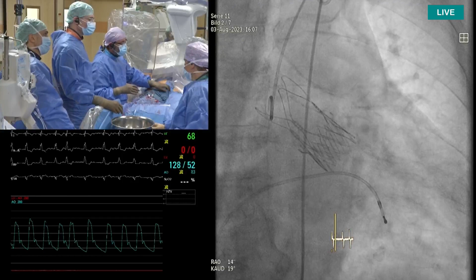If I can make just one comment, I think for the audience it's important to highlight that, contrary to other self-expanding devices where a shallow implant has been recommended to reduce pacemaker rates, with this device, if you want to take full advantage of the radial forces, you have to deploy it at the exact position as Mohamed did just here. A shallow implant would increase the risk of a pop-out and would increase the risk of PVL. So it's very important that a shallow implant is not used in this device.